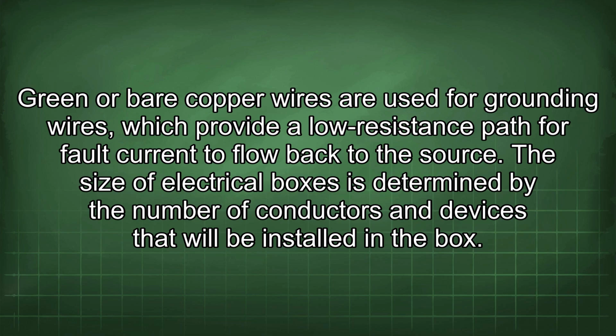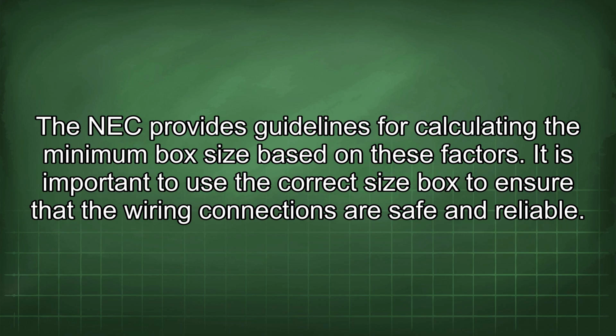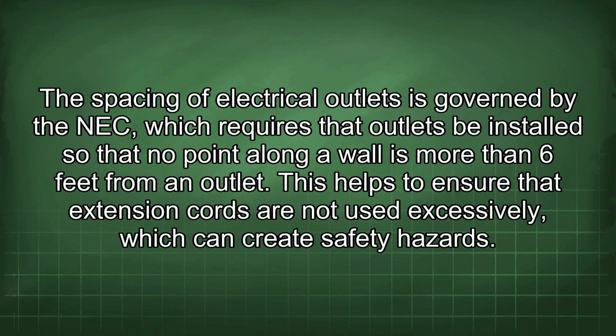The size of electrical boxes is determined by the number of conductors and devices that will be installed in the box. The NEC provides guidelines for calculating the minimum box size based on these factors. It is important to use the correct size box to ensure that the wiring connections are safe and reliable. The spacing of electrical outlets is governed by the NEC, which requires that outlets be installed so that no point along a wall is more than 6 feet from an outlet. This helps to ensure that extension cords are not used excessively, which can create safety hazards.